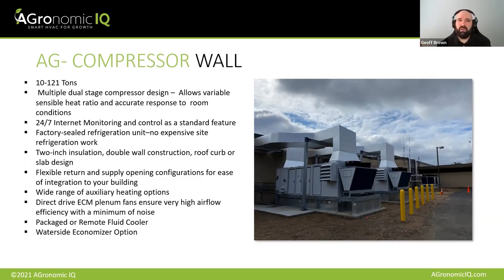And so it means that in particular with low ambient conditions, when it's cold outside, we're able to still do full cooling and dehumidification without having the compressor circuit need to work in a minus 20 or minus 30 or minus 40 degree environment. And we have these units successfully deployed in places like Edmonton that are unnecessarily cold, and people, frankly, I struggle to understand why people live there. Different story for another day.